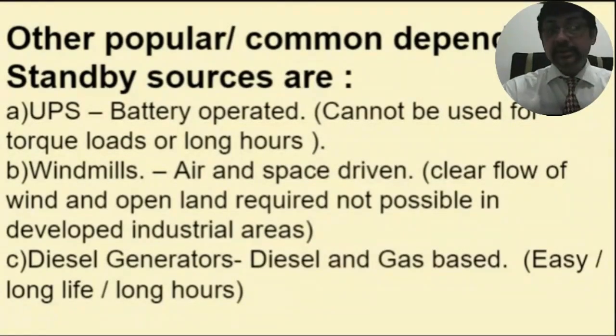So the third is diesel generators. Diesel generators are diesel based and gas based. Of course, we have smaller generators which come with petrol start, kerosene run, or petrol start and petrol run. But diesel generators in industry are the most popular because they can run for long hours. At the same time, they have a long life. The space investment is not as high as in windmills, and they handle the other technicalities which UPS is many times not able to take care of.